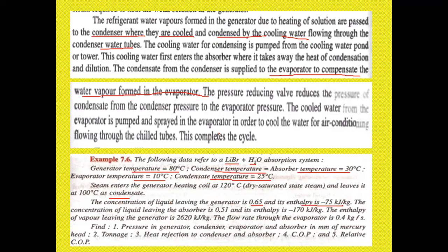Now the concentration of liquid leaving the generator is 0.65 and the enthalpy is minus 75. The concentration of liquid leaving the absorber is 0.51 and the enthalpy is minus 170. The enthalpy of vapor leaving the generator is 2620 kJ per kg. The flow rate through the evaporator is 0.4 kg per second.